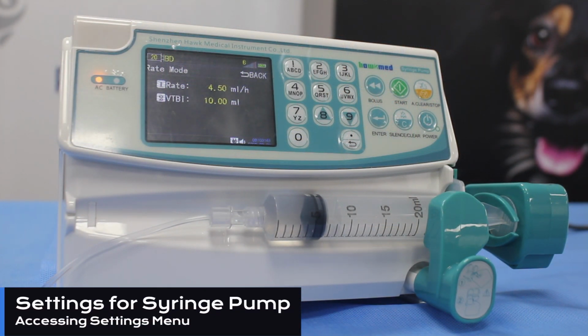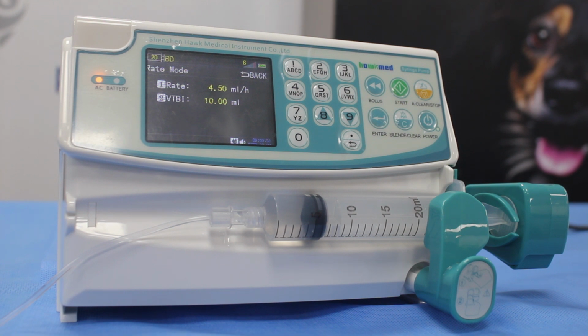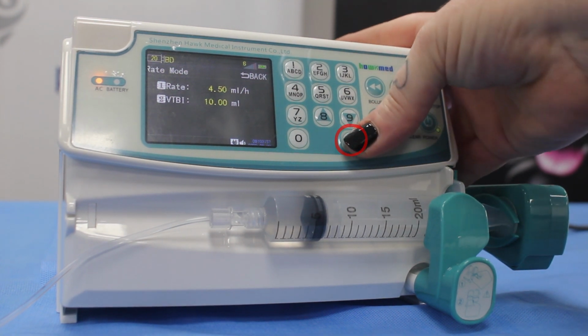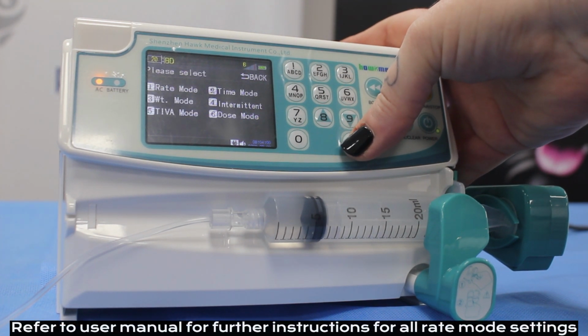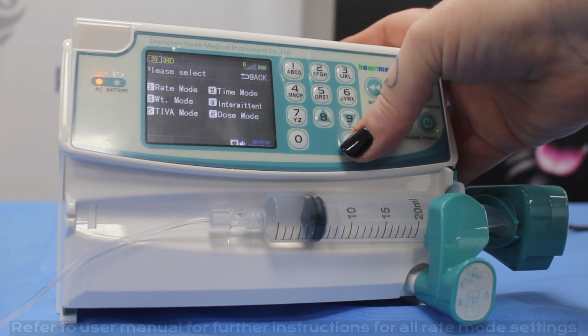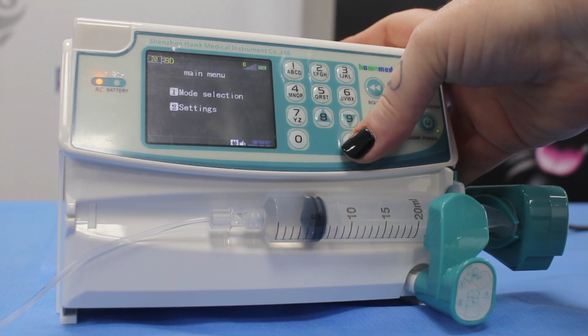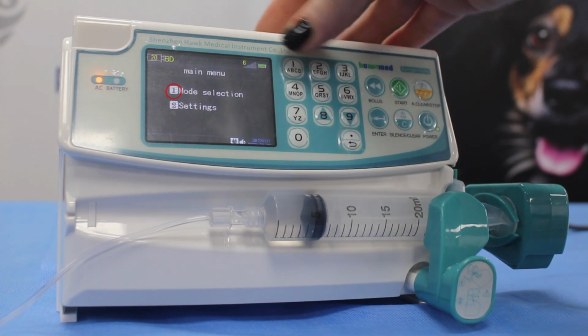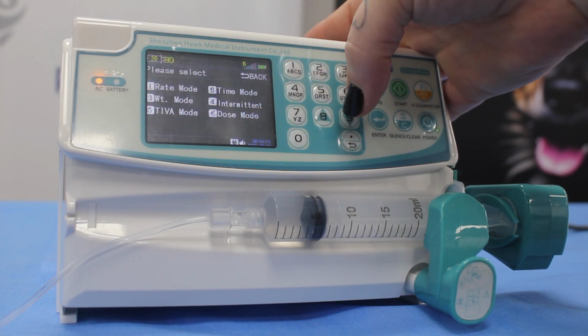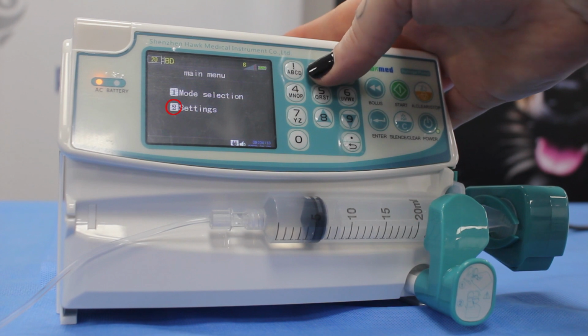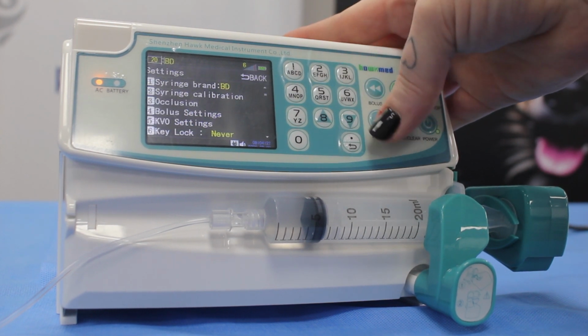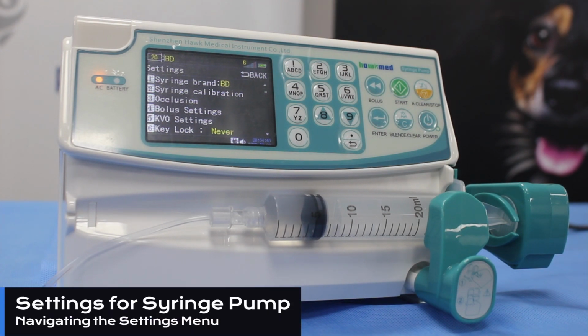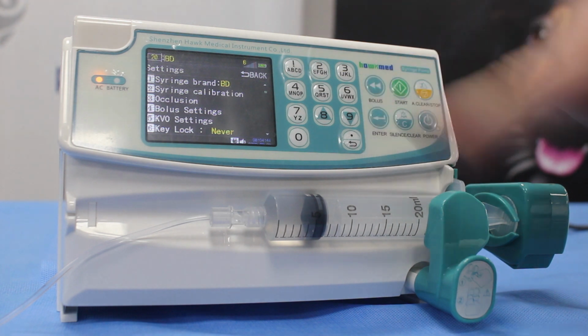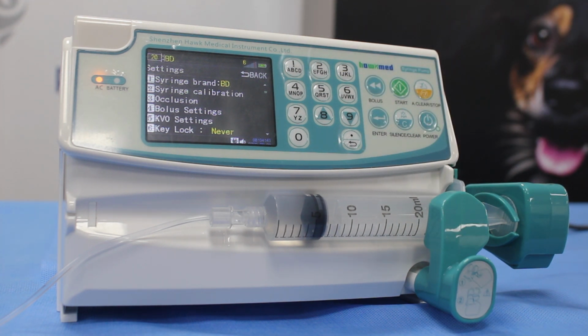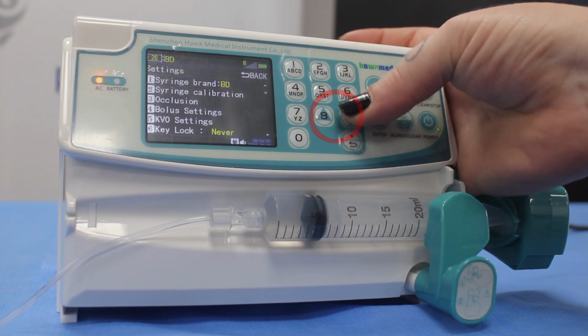We can access our settings for our Hawkmed syringe pump from any screen that's currently being displayed by pressing the back button. Going from the rate mode will first put us back in the screen for all the additional mode options that we can use. Pressing back again will put us in the main menu, which again has the mode selection, which is the one we've just come from, which is number 1 with all the different functions for your mode settings. Going back again, number 2 is going to take us into the full settings list. We can navigate the settings list by using the numbers corresponding to the keypad to enter any of the settings required. We can also see additional settings to adjust by using your up and down arrows and your 8 and 9 key to move through this menu.